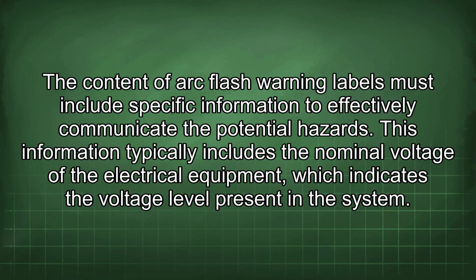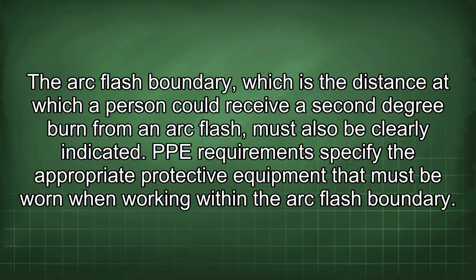The content of arc flash warning labels must include specific information to effectively communicate the potential hazards. This information typically includes the nominal voltage of the electrical equipment, which indicates the voltage level present in the system. The arc flash boundary, which is the distance at which a person could receive a second-degree burn from an arc flash, must also be clearly indicated. PPE requirements specify the appropriate protective equipment that must be worn when working within the arc flash boundary.